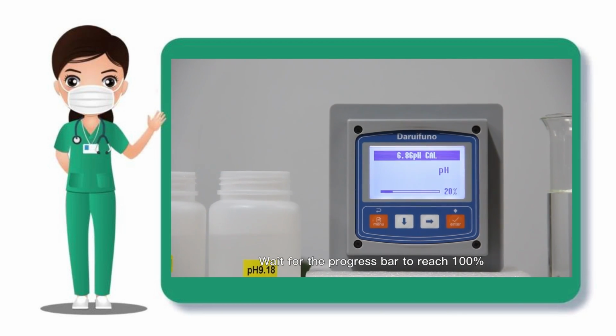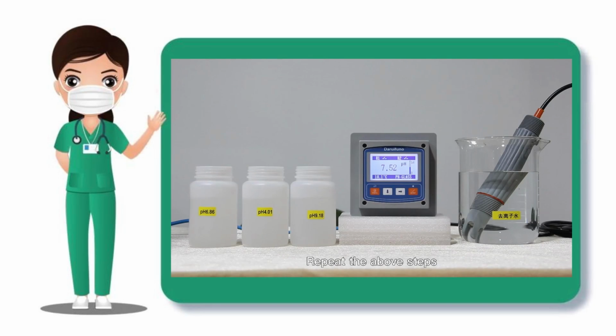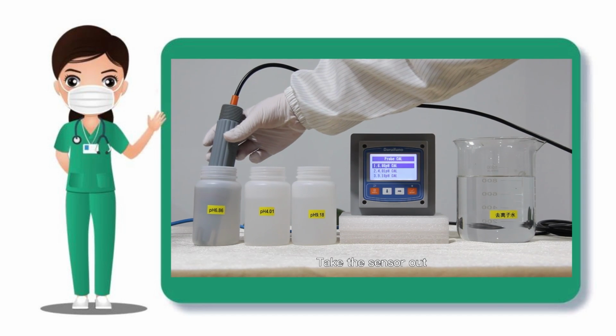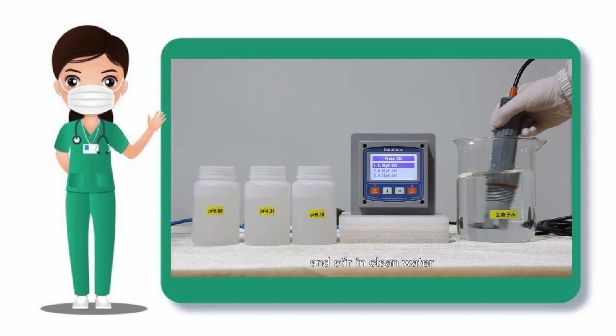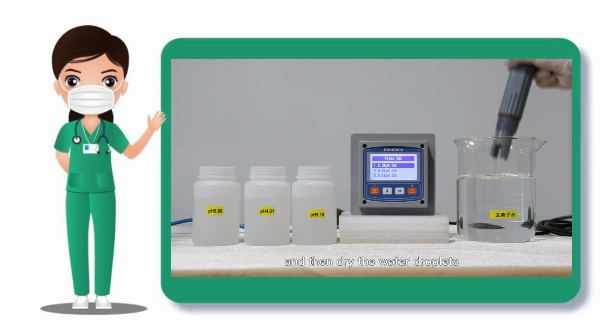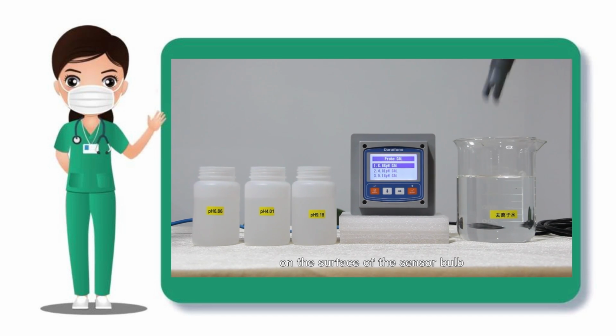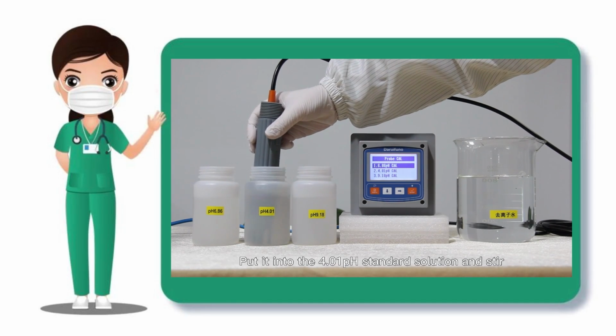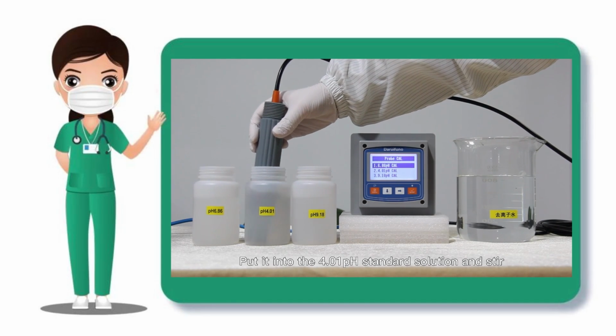Wait for the progress bar to reach 100%. The screen displays success. The zero calibration is completed. Repeat the above steps and put in 4.01 and 9.18 respectively according to the prompts. Take the sensor out and stir in clean water, and then dry the water droplets on the surface of the sensor bowl. Put it into the 4.01 pH standard solution and stir.